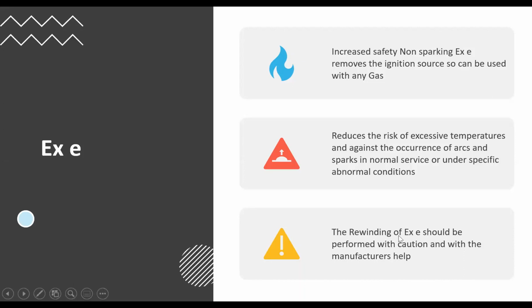The rewinding of EXE should be performed with caution and with the manufacturer's help, because the windings of an EXE have been designed specially, never to be stressed, never to be put under load. They have a special insulation system, special varnishes, special winding techniques. If you can get the information from the manufacturer, perfect. If not, just be careful.